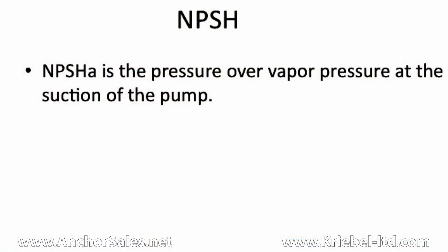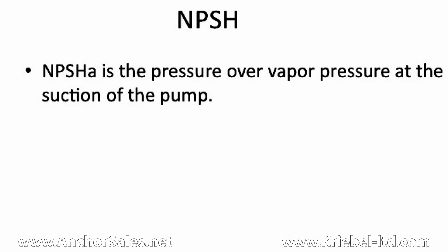NPSH stands for net positive suction head. There are two NPSHs. NPSHA, which is the net positive suction head available in the system — this is the pressure above vapor pressure of the liquid at its pumping temperature. It's that simple.